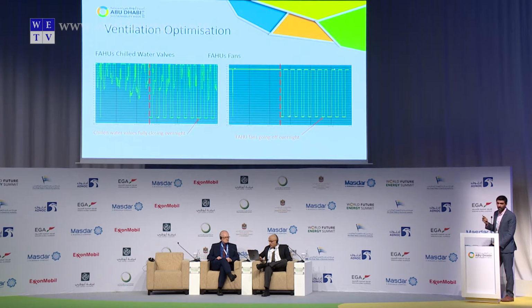Here is a screenshot I took from the BMS in Masdar City, where we once noticed overconsumption on one of the fresh air handling units on the ventilation system. When we looked closely at the BMS, we noticed that if you look at the left side, the cooling valve was not closing at all. So even in the weekend, in the night, it wasn't closing. And the fan was also continuously running. So it was obvious to us that the machine is running 24 hours, 7 days a week. When we simply tuned the time schedule of that air handling unit, you see that after we implemented the measure, the chilled water valve is closing automatically, which is a good sign when the fan is off, and the fan is turning off in the night and in the weekend.